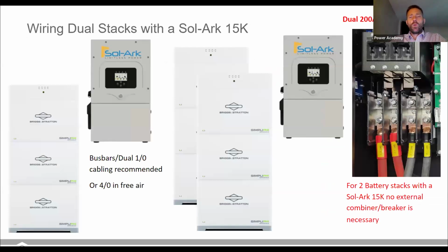Want to point out the 2 options here with Sol-Ark 15K. For a single stack of 3 batteries, you've got enough power to run this. Your backup duration will ultimately depend on how rapidly the customer is using power, what their loads are, and how quickly they're going to use that energy. Our common configurations include installations which have 4 stacks with the single Sol-Ark inverter. Commonly, we're seeing customers install 1 or 2 stacks of batteries with a 15K inverter. It gives you anywhere between 12 hours of backup for a heavy user on the single stack to maybe 24 hours for an average user. 2 stacks can give you a couple of days of backup.